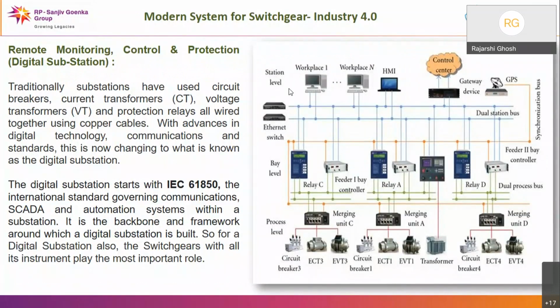Here we have three levels of instruments. Number one is the process level or field level, that is the circuit breaker, transformer, whatever the field equipment is. There the sensors are there, and from the sensors, there is a merging unit. So from the equipment to the merging unit, it is known as the field level or process level. From the merging unit to the bay controllers, which control all the activities for the bays, this is called the bay level. And from the bay to the control room, it is called the station level. So these are the main few steps: the process level, bay level, and station level. This is the architecture of a digital substation.